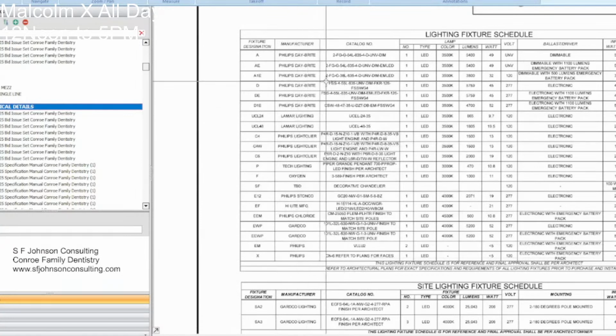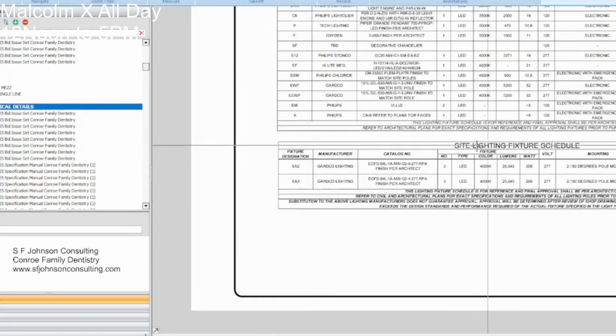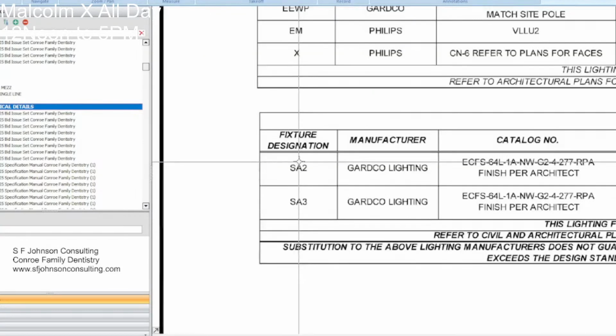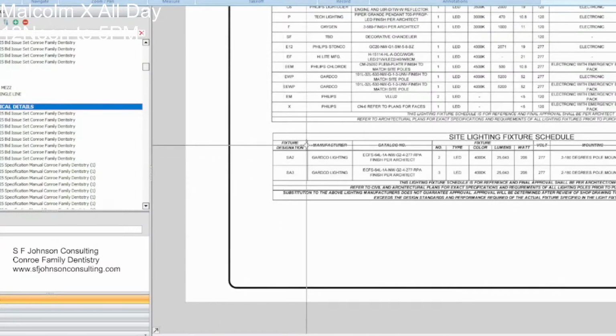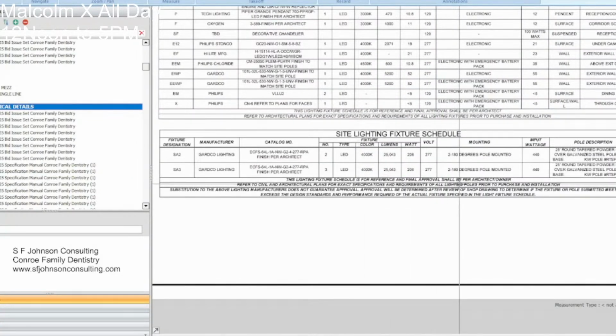Or it'll be noted like that on the plan. Also, site lighting, make sure you look at the details of your site lighting. I need to go back and put a video on that, because chances are you're going to need a 3/4 inch ground wire and a grounding rod for each of the light fixtures.